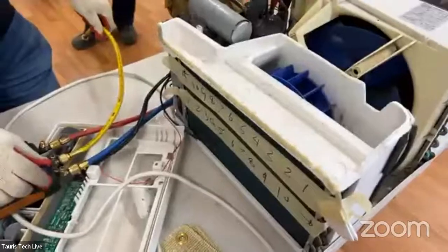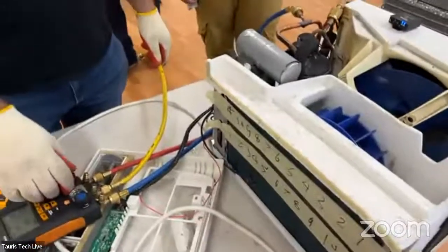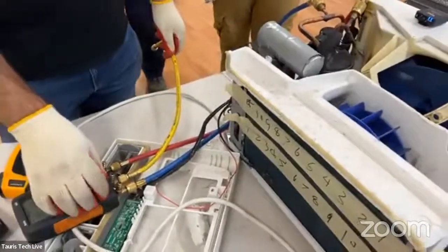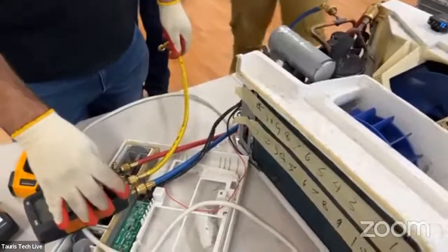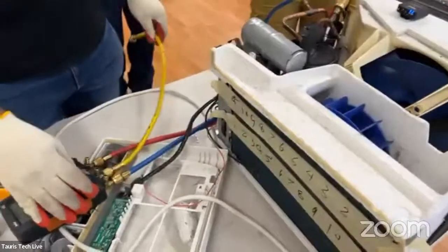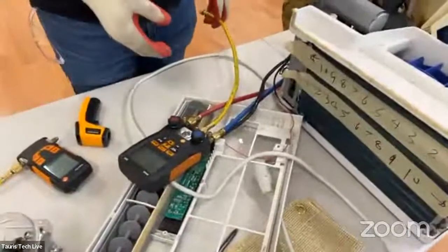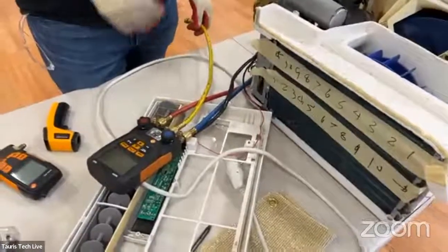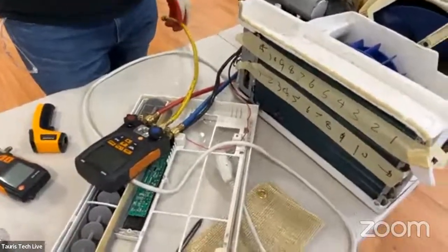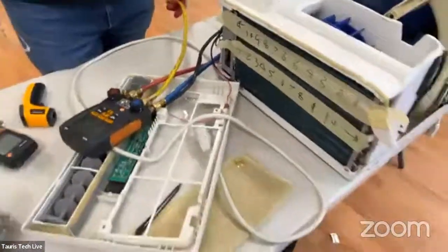Now, think about how small of a machine this is. We're setting up heat pump jobs with 200, 300, 400 feet of refrigerant line. So you can imagine how much nitrogen has to go in there. That's why most people don't do it. And how about the big machines, like the buildings? You have a 1,000-ton chiller. They're supposed to fill it with nitrogen. So how much nitrogen do they need for that? It depends.